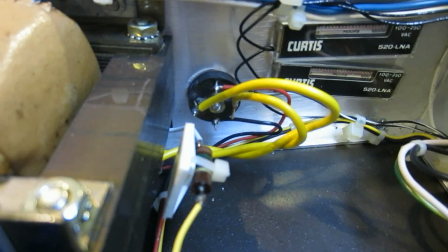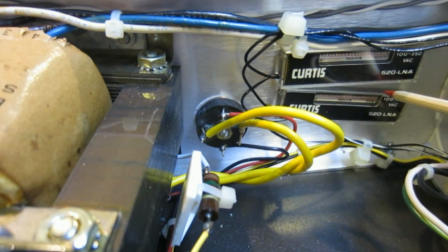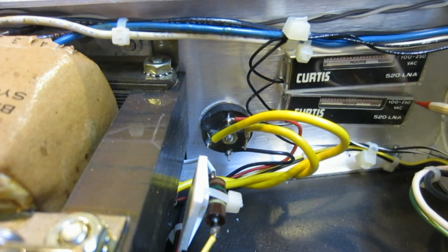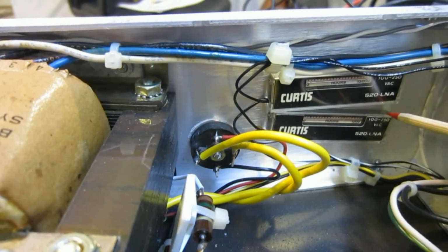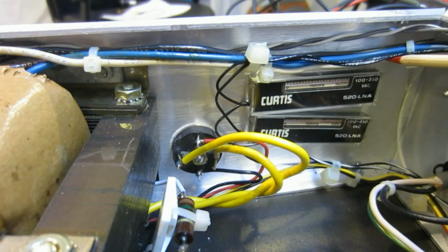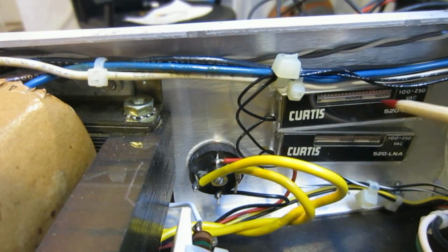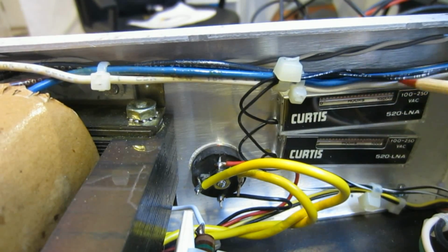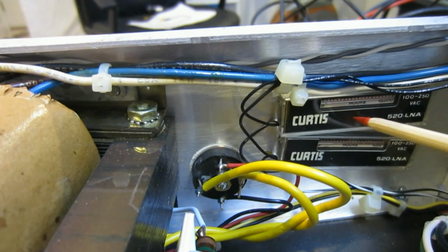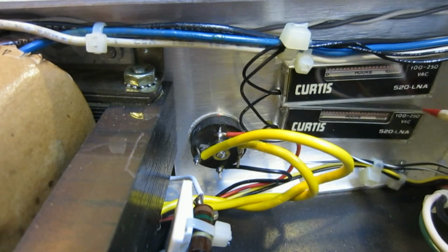Actually, I'm not sure if you guys know what this is, but back in the days, these were routinely used to see how long the instrument has been powered on. So this one has 2 units, and each one is, I'm not sure if you can read it, 10,000 hours. So right now, the mercury inside already points to 10,000 hours. Which means this thing has been powered on for at least that much time.